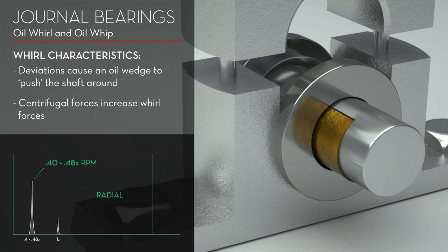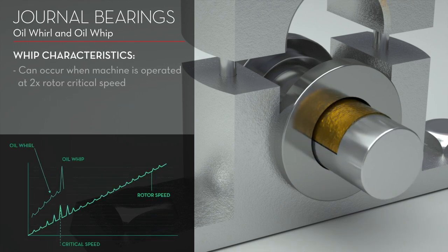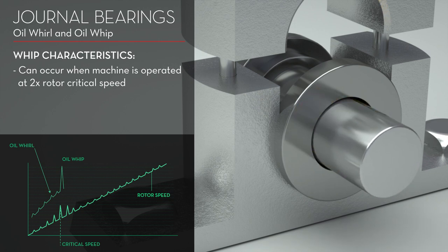It appears on a spectrum at 0.40 to 0.48x of RPM and is quite often severe. Oil Whip can appear when the machine is operated at 2x rotor-critical speed. This spectral map shows when Oil Whirl becomes Oil Whip instability as shaft speed passes through 2x rotor-critical speed.